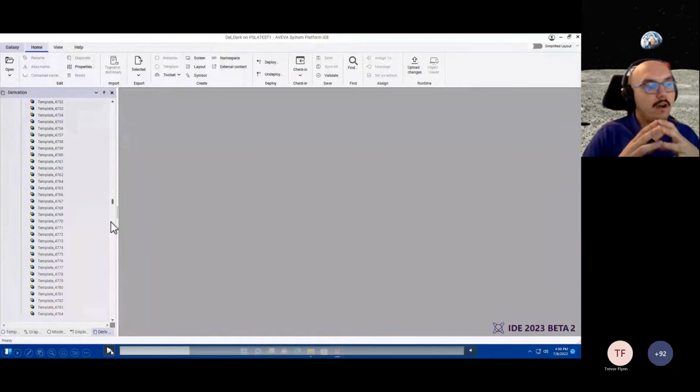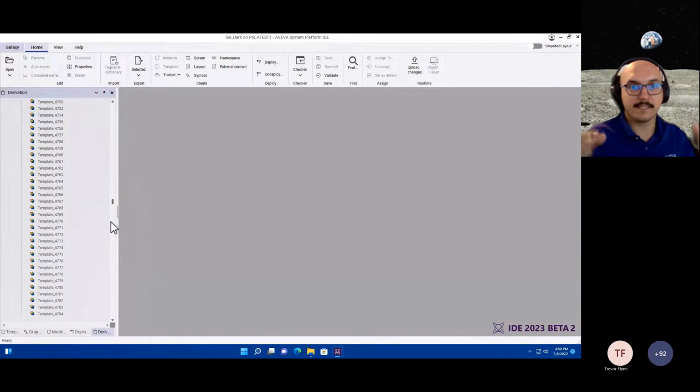Object wizards are a way of creating a polymorphic template that includes all the permutations and combinations that an asset class might have. Maybe slight deviations of a motor being a 5 horsepower motor or a 20 horsepower motor, or maybe it's from a different vendor and there are slight configuration changes. Instead of creating a sub template and a long list of hierarchy, there is the option to create an object wizard, which acts as a polymorphic master template.